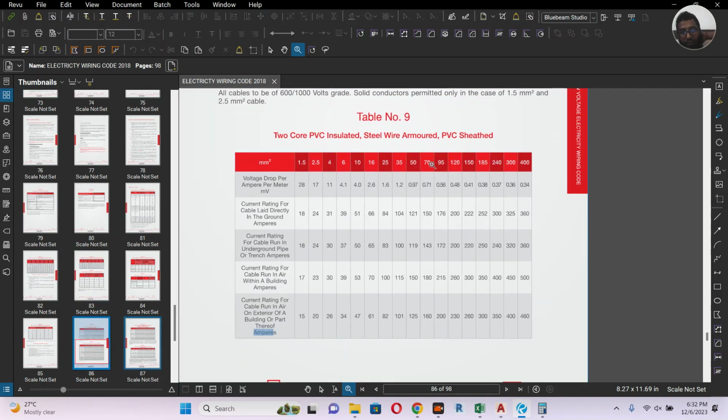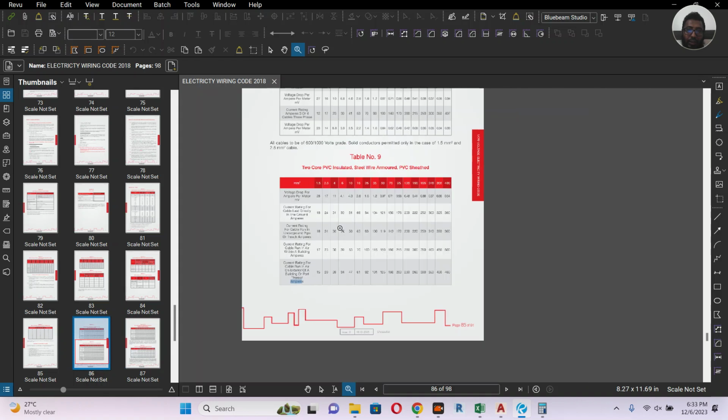Whichever cable you are using, that one you have to select. But this again, as per the Kahramaa regulation, meaning Qatar regulation, if you are in another country, you have to use their catalog. You can also use the catalog of the cable manufacturer. In Sri Lanka we have Kelani Cables, they have their own catalog, we can check. What I am going to check now, the same thing you can check there also.